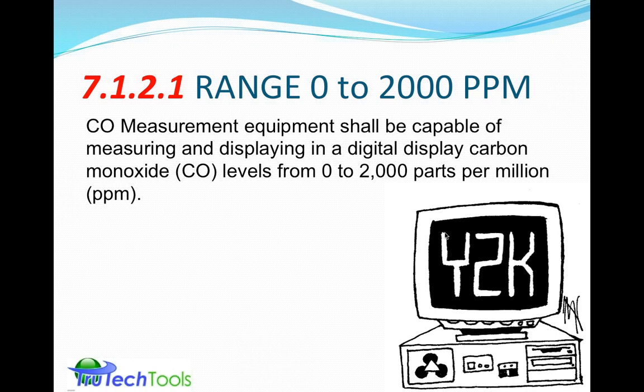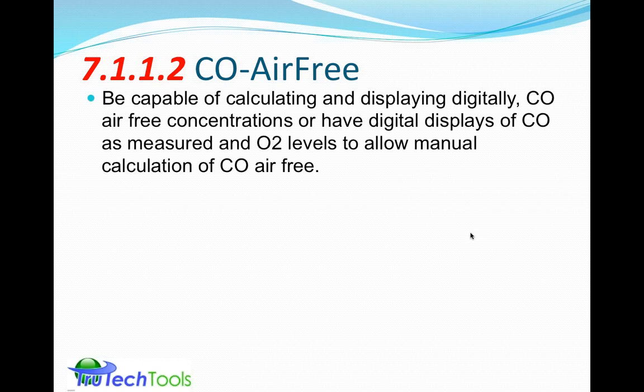7.1.2.1 talks about a range of 0 to 2,000 parts per million, and looking for equipment to measure and display digital carbon monoxide levels from 0 to 2,000 parts per million. So that's a pretty easy achievement for most of the meters on the market. It adds in the additional criteria of CO-AirFree, 7.1.1.2. What that is, it's looking for the capability to calculate and display digital numbers for CO-AirFree calculation, or have an oxygen and CO level displayed so you can manually calculate CO-AirFree.